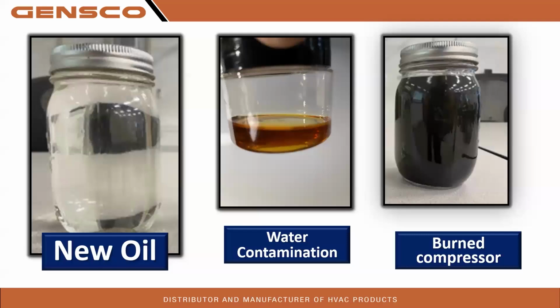The oil in the jar on the left is brand new oil. You can see it pretty much looks like water, crystal clear. The one in the middle came out of the same unit that I showed the ugly, nasty windings in. That one was described as having green slime coming out of it. It was from water damage. Water actually in that unit caused that. And of course, the oil on the right, that's a burnt compressor. But the oil should look like the one on the left.